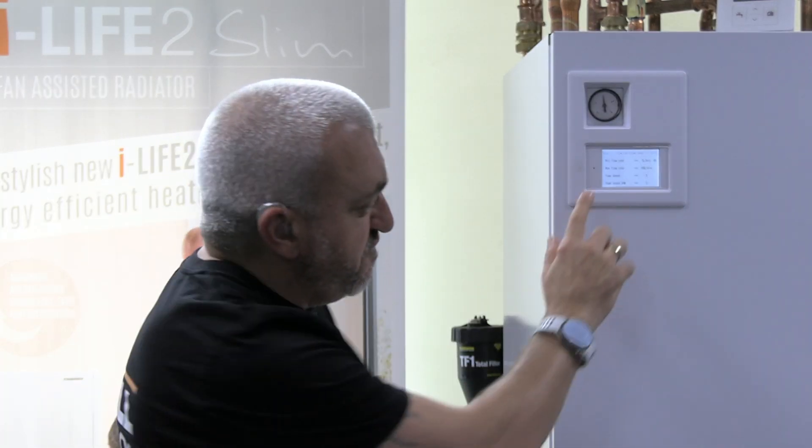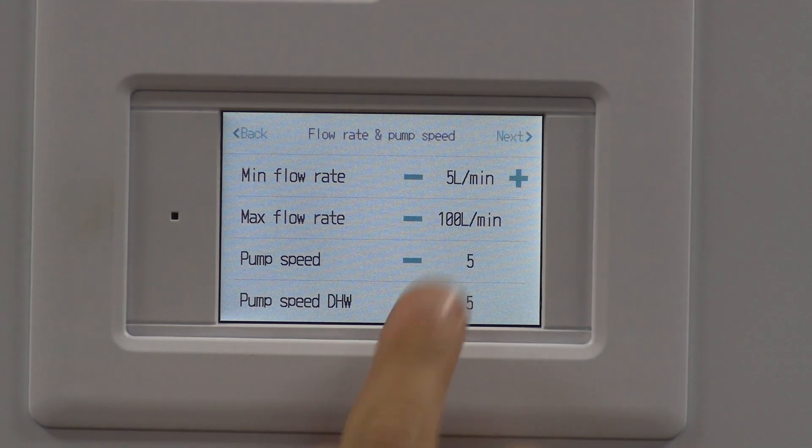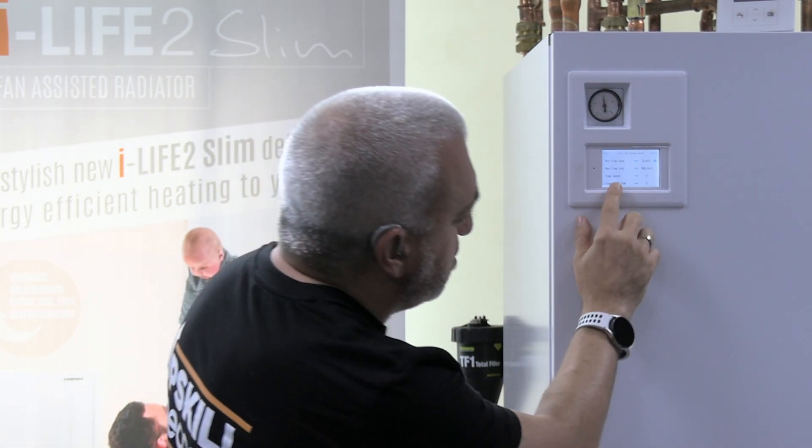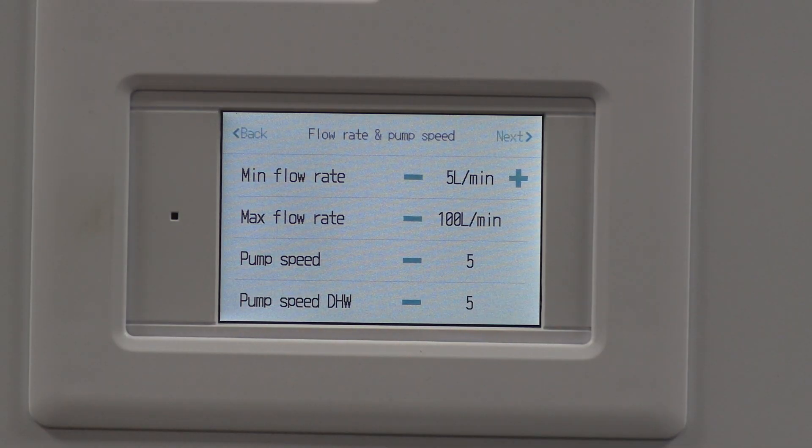The next setting covers flow rates - these are the thresholds at which the sensor will trigger a fault. The minimum is five and maximum is 100 litres per minute; if it exceeds 100 or drops below five it will fault. Those are standard settings you'd normally keep. Then there's pump speed - I'd always recommend starting on high pump speed to push all the air out of the system and get the glycol cycled around and blended with the water. You can always turn the pump speed down later to suit your delta T.